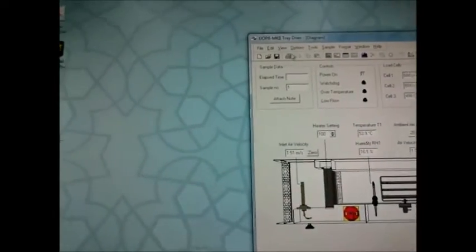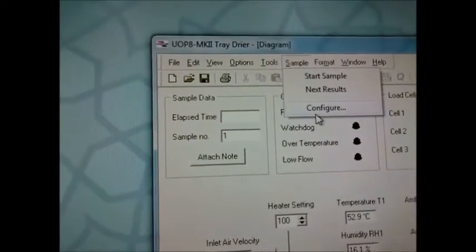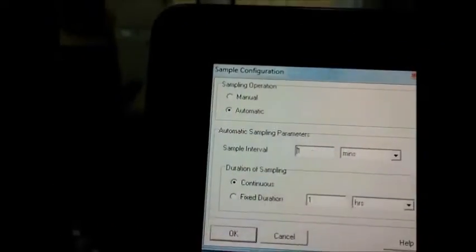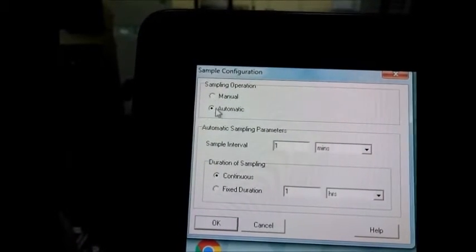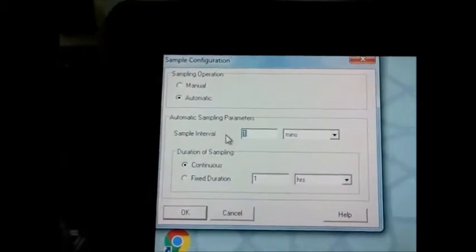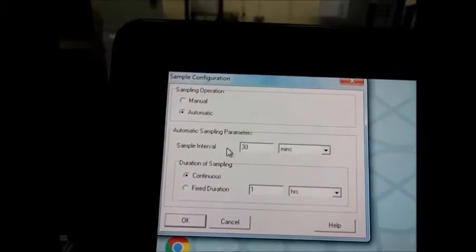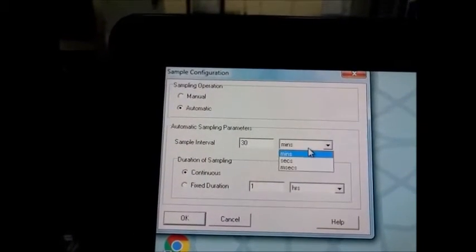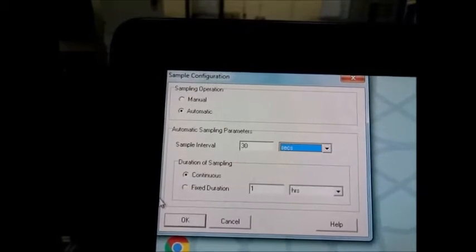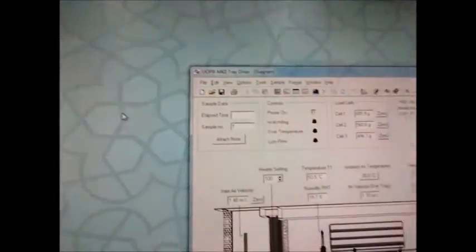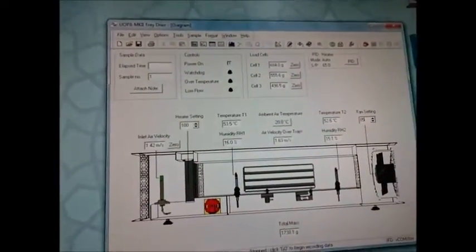Now we can go to sample configure to adjust the time of sampling to make it automatic. If you make it manual you have to press it every time. We'll make sample intervals every 30 seconds. It's recommended to make it every 2 minutes, but for here we'll make it 30 seconds.